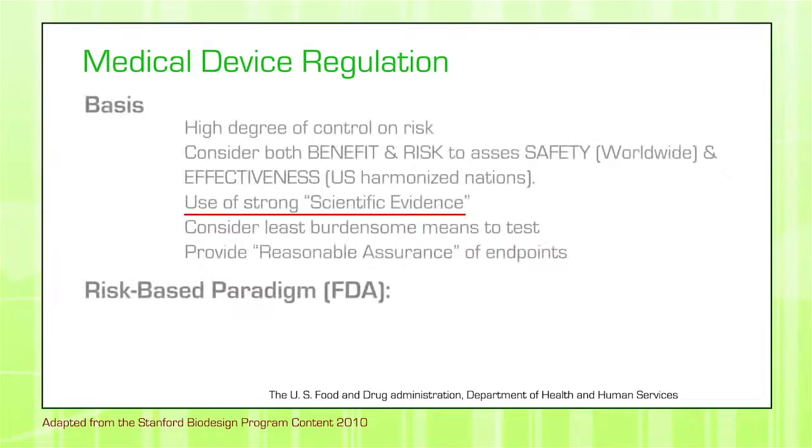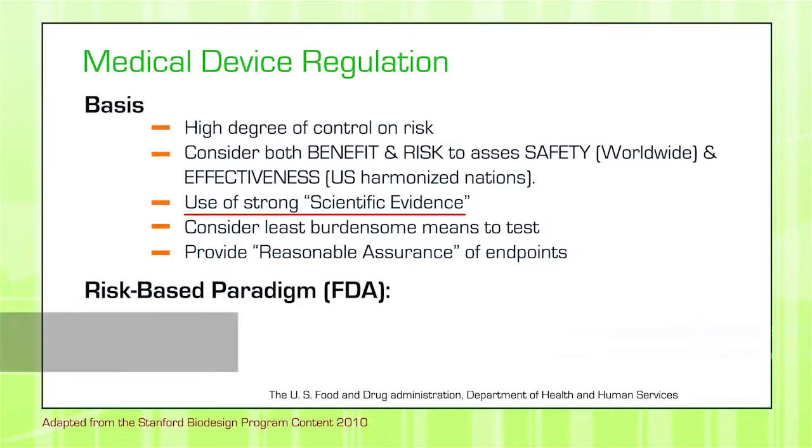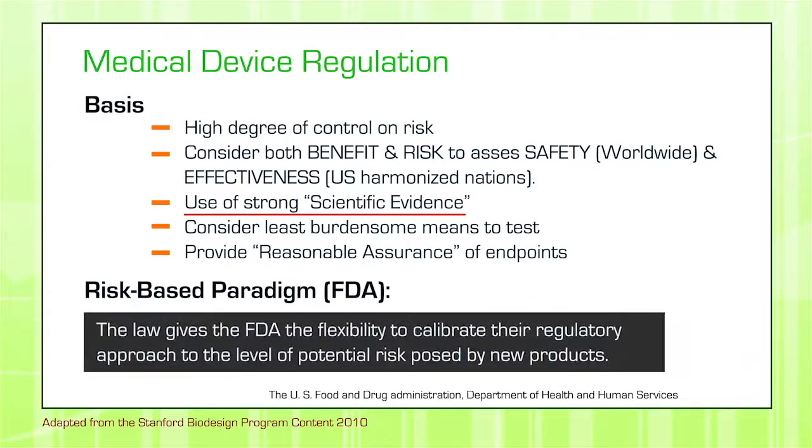Another characteristic that is basic for medical device regulation is the use of strong scientific evidence. It must be shown quantitatively and without any doubt that there is enough scientific evidence to show that this device is safe, and in the case of the US, if it's effective.